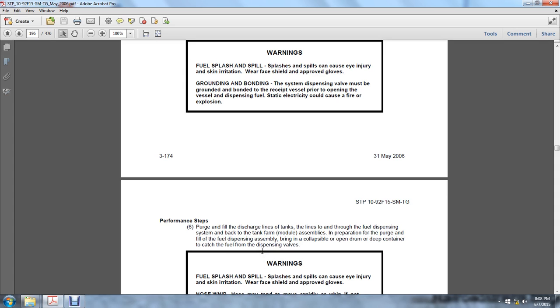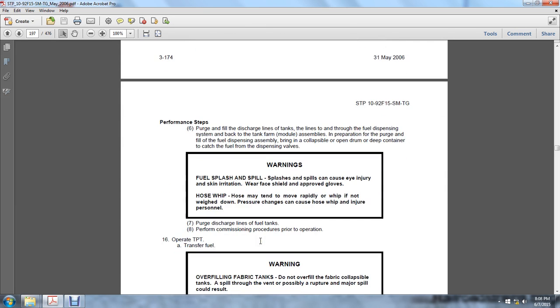Purge the fill of the discharge line of the tanks and the lines through the fuel dispensing system back to the tank farm module assembly in preparation for the purge of the fuel dispensing assembly. Bring in a collapsible or open drum or deep container to catch the fuel from the dispensing valves. Fuel splash and spill: splashes and spills can cause eye injury and skin irritation. Wear face shield and approved gloves.